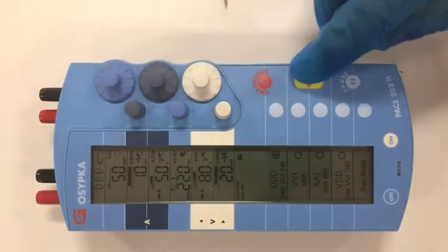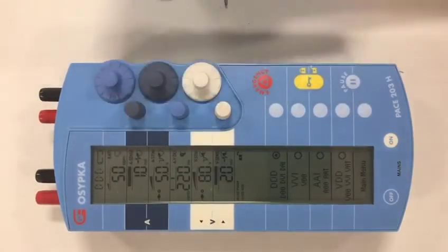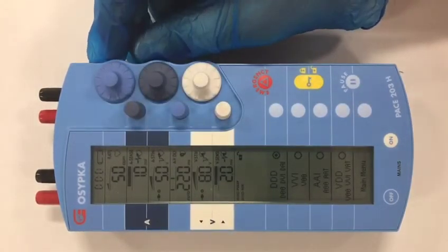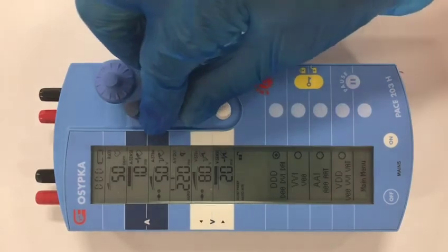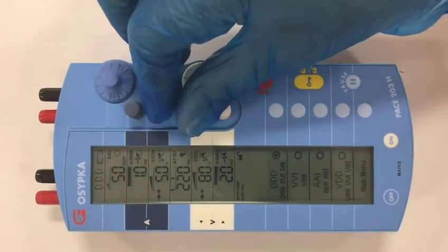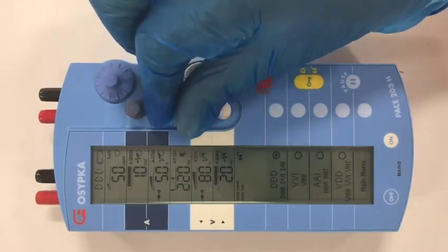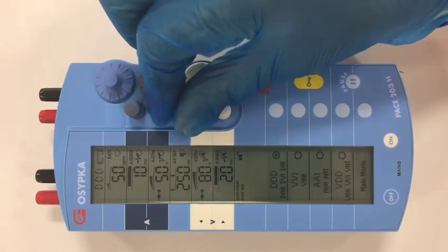Now, no sooner have you learned that the two are tagged together, then you will ask, how can I separate the two? Because there are times when you need a very long AV delay, and the quick way of doing it is just to give the AV delay control a twist to one side, and then you can now independently program the AV delay.